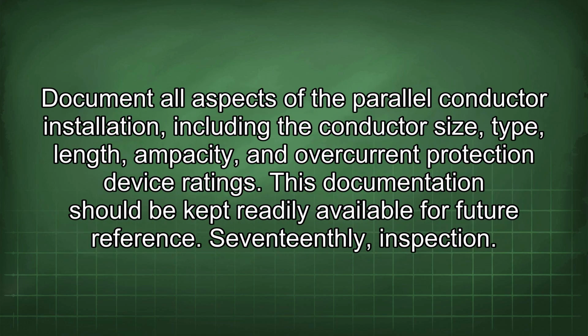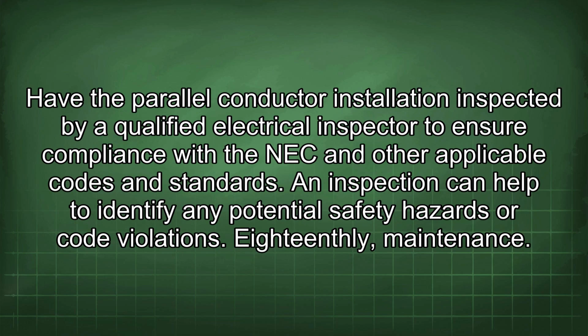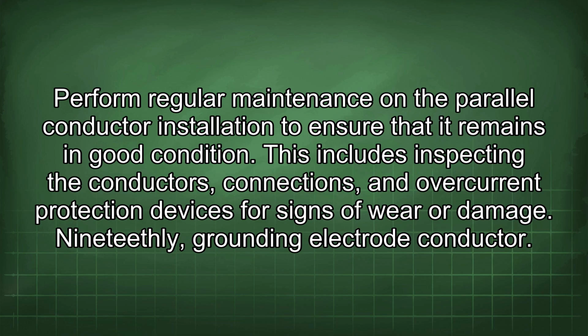Document all aspects of the parallel conductor installation, including the conductor size, type, length, ampacity, and overcurrent protection device ratings. This documentation should be kept readily available for future reference. 17th, inspection. Have the parallel conductor installation inspected by a qualified electrical inspector to ensure compliance with the NEC and other applicable codes and standards. An inspection can help to identify any potential safety hazards or code violations. 18th, maintenance. Perform regular maintenance on the parallel conductor installation to ensure that it remains in good condition. This includes inspecting the conductors, connections, and overcurrent protection devices for signs of wear or damage.